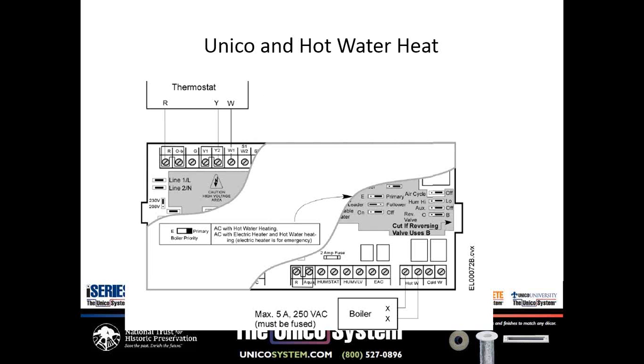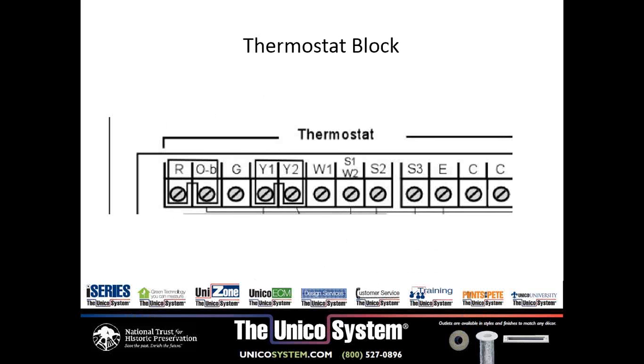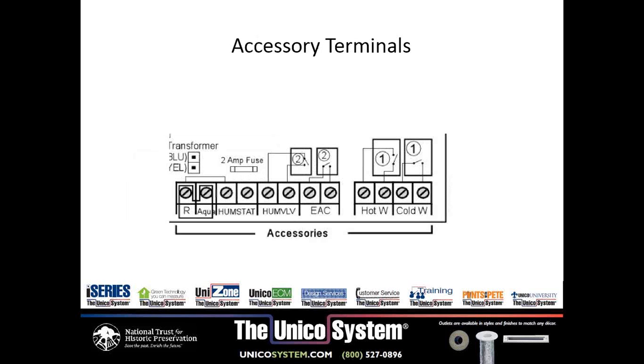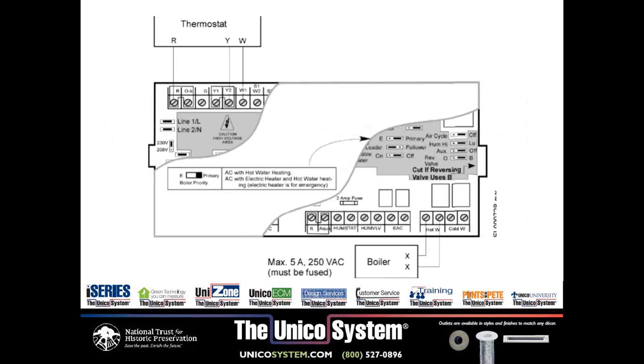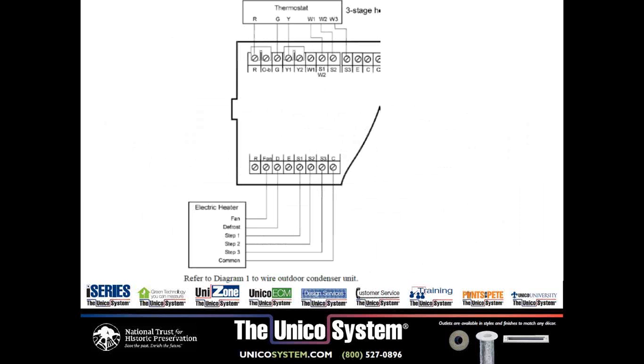This is the wiring schematic. They're very simple to hook up. This is our EC motor. It's the same wiring that you would use with any other thermostat block. The accessory terminals here, if you're using a boiler, you see these two terminals labeled hot water. That is a 250-volt dry contact. You just hook that up to the boiler, the valve, or the pump, and that will energize the hot water. If you're using electric furnaces, we'll talk about those later, you can energize those, so when you go to S3, or stage 3, it will shut off the outside unit and bring on the third stage of emergency heat. So again, very simple to do. We have all these wiring diagrams in the installation manual.